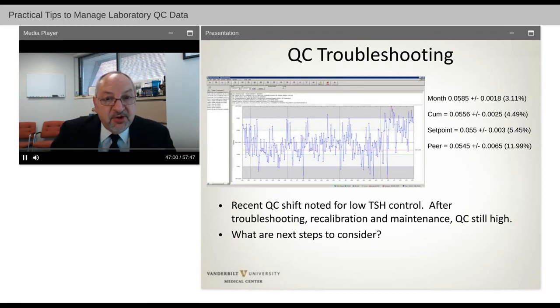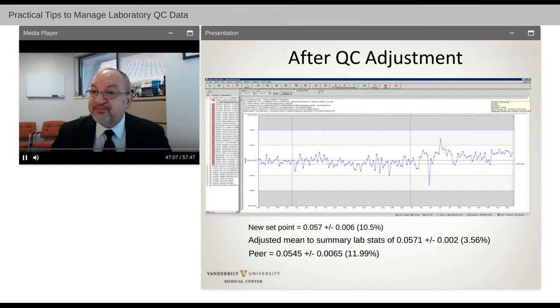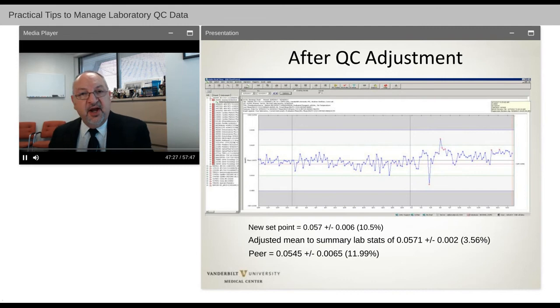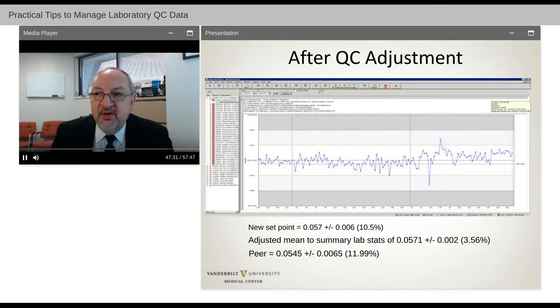We've done multiple troubleshooting, recalibration, maintenance, but the QC is still running high. So the next step to reconsider is really changing the set point across all of our analyzers. We had four or five analyzers that were running TSH. We set the set point to the mean of those and adjusted our CV upwards to closer to 10%, which made it closer to our peer group. And now look at the plot. You can see that many of these outliers in red dots that we had been troubleshooting before were really within reasonable performance for that particular methodology. And we probably were over troubleshooting with this. So it's something to always keep in mind and consider.